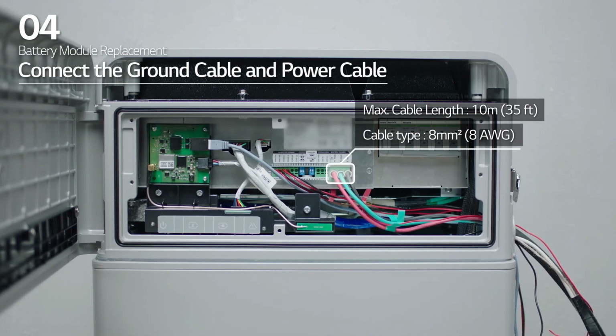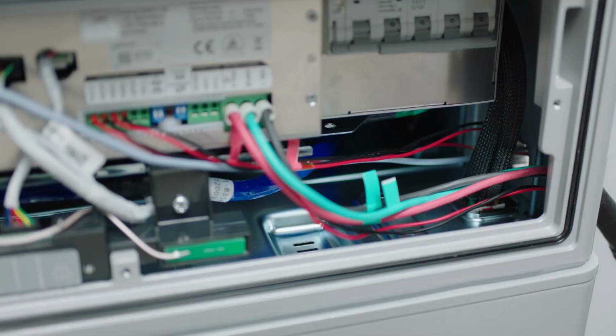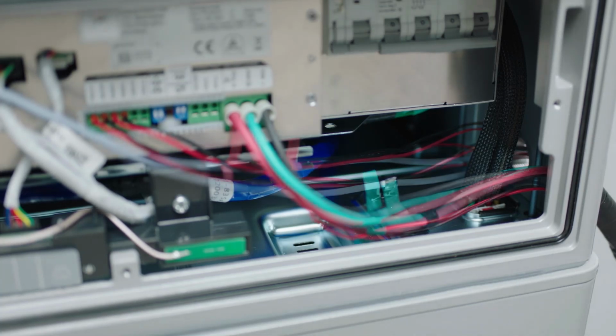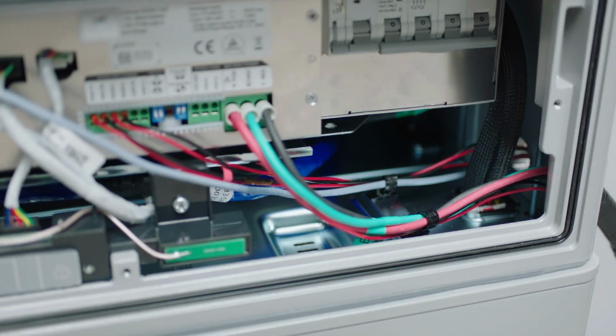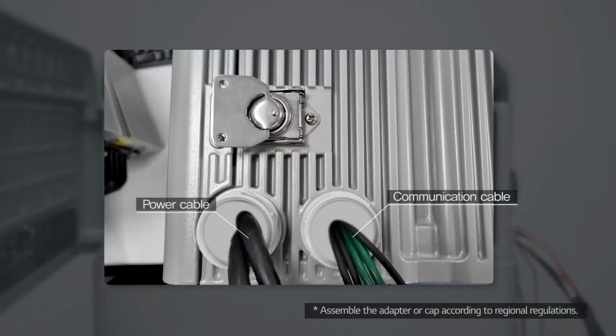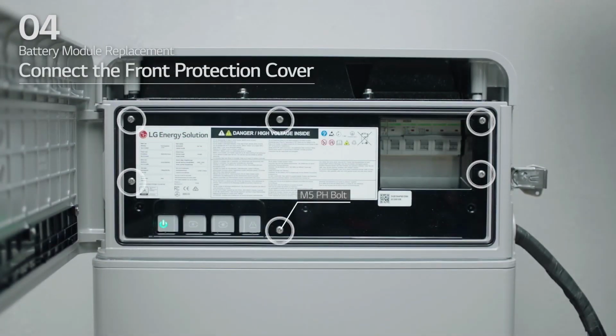Connect the ground cable and power cable. Arrange the power cables and communication cables separately using cable ties. Then, apply silicone sealant or putty around the cables at each hole to prevent foreign materials from entering the battery pack. Connect the front protection cover using 6 M5 panhead bolts.